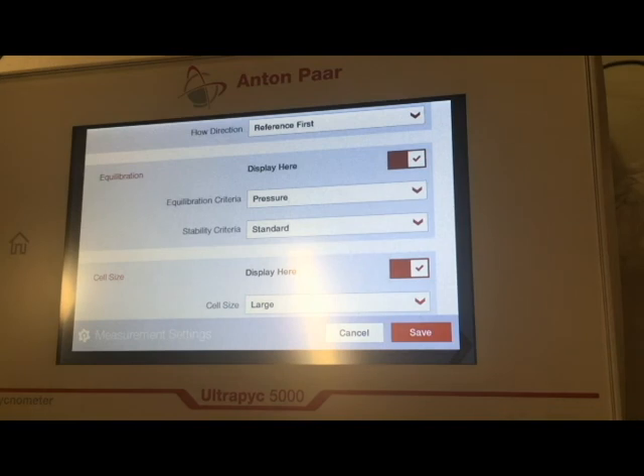The next most precise option is pressure. That means that it is going to wait for the pressure to stabilize fully before moving on to the next cycle. We don't know how long that's going to take. That's going to be kind of based on your sample and the internal workings of the machine.